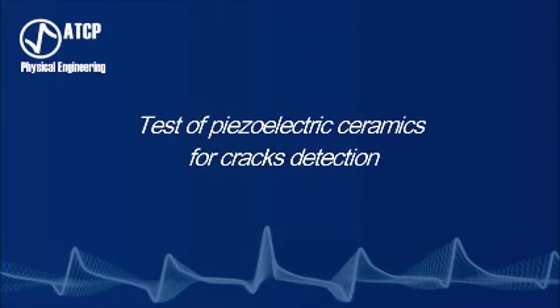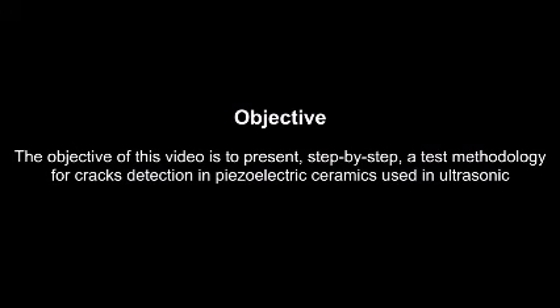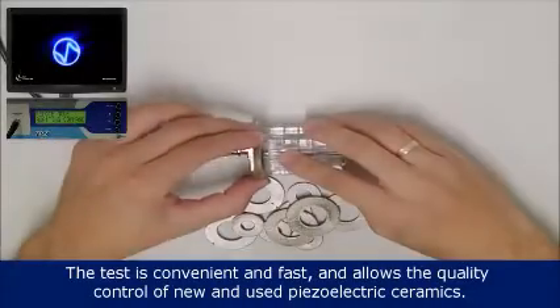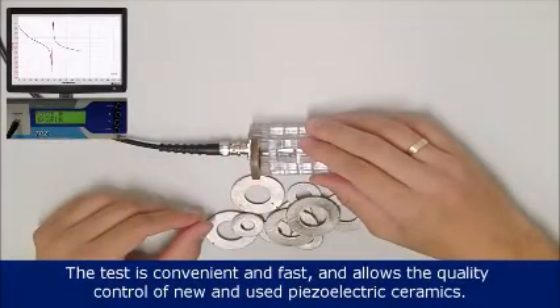Test of piezoelectric ceramics for cracks detection. The objective of this video is to present step-by-step a test methodology for cracks detection in piezoelectric ceramics used in ultrasonic power transducers and converters. The test is convenient and fast, and allows the quality control of new and used piezoelectric ceramics.